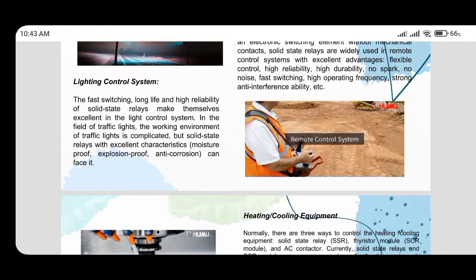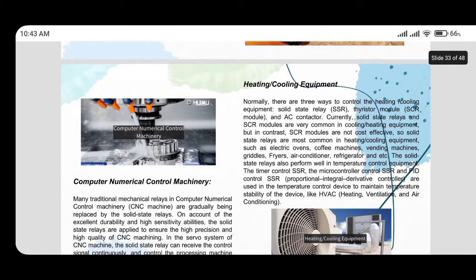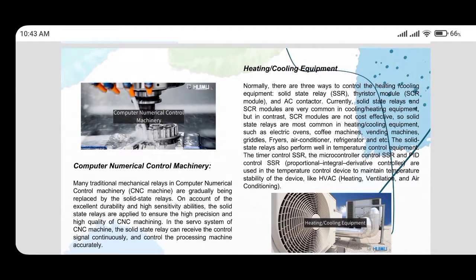The third is heating and cooling equipment. Normally, there are three ways to control heating and cooling equipment: solid state relays (SSR), SCR modules, and AC contactors. Currently, solid state relays and SCR modules are very common in heating and cooling equipment, but in contrast, SCR modules are not cost effective. So solid state relays are most common in heating and cooling equipment, such as electric ovens, coffee machines, vending machines, griddles, fryers, air conditioners, refrigerators, and so on.